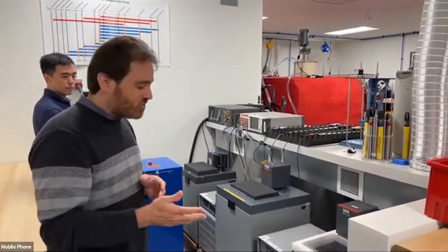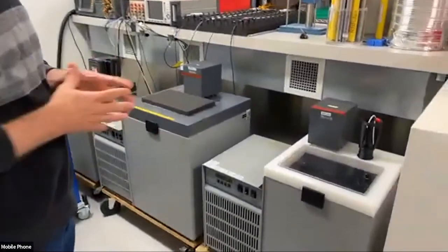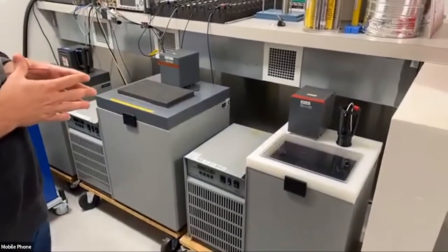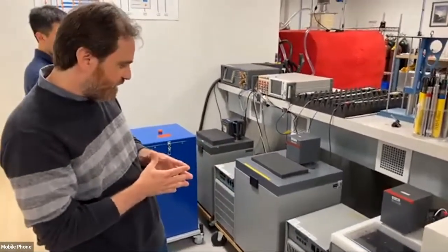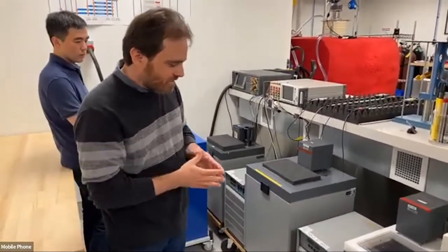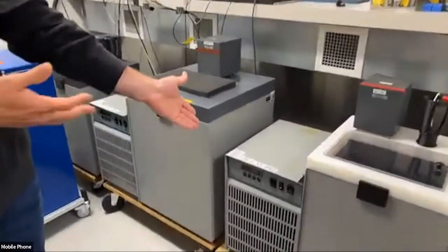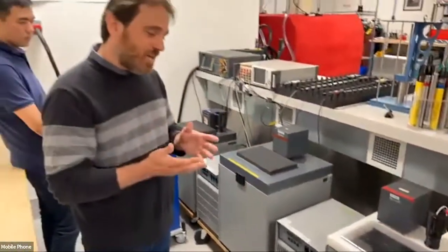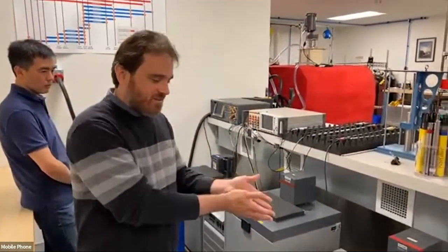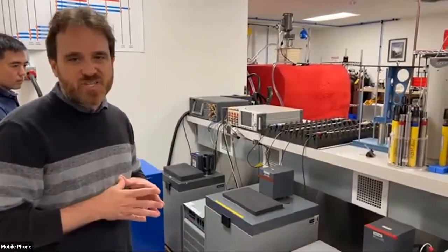The way we accomplish that is by immersing each instrument in our fluid baths. In this case, we're using Hart Scientific 7035 baths, if I'm not mistaken. Here we see one example of it, which is currently close to 0 or -5 degrees. So we take your instrument, immerse it in this fluid bath, and then start the 8-point calibration cycle.